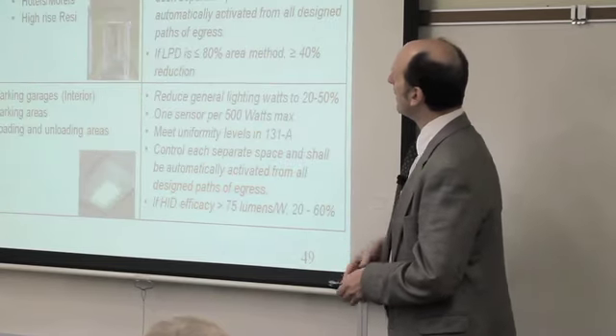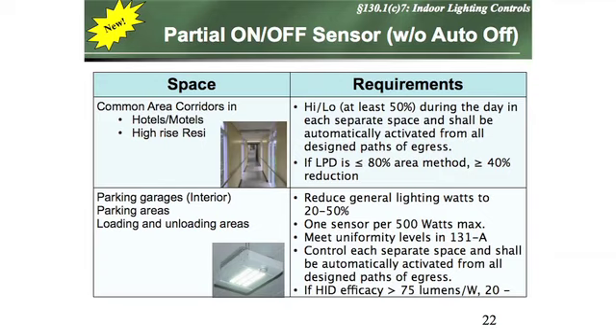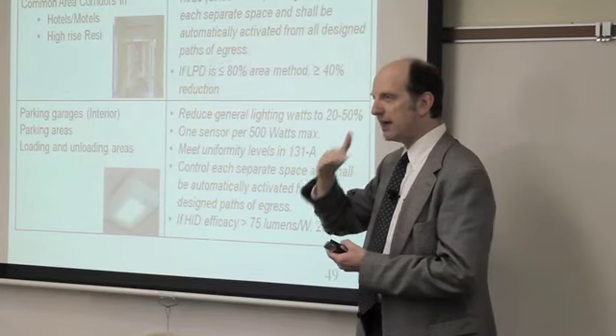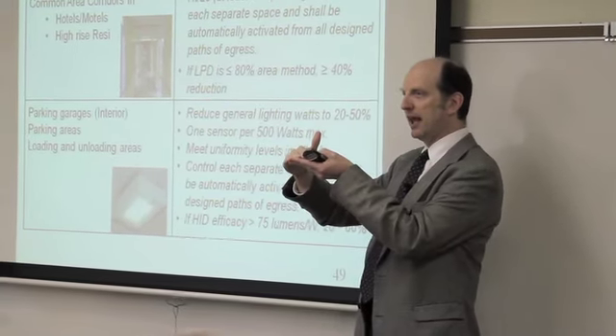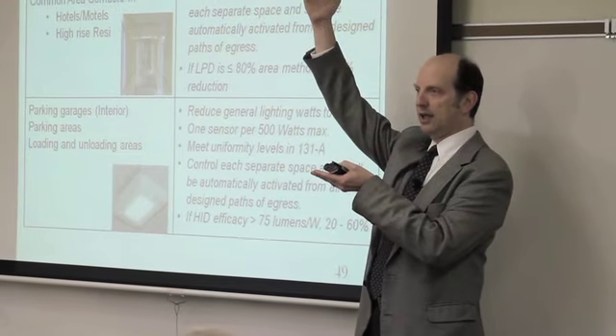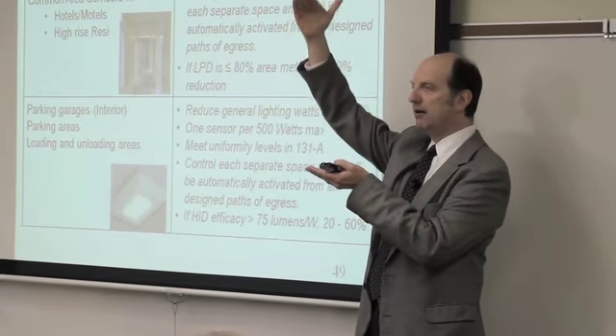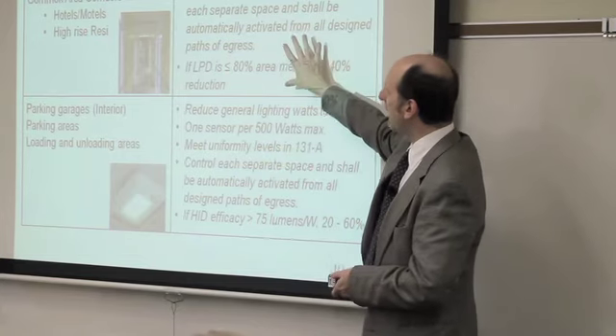All right. That same idea of partial on and off they have for other spaces, except this is where there's no automatic off. So partial on-off for corridors and hotel, motel, multi-dwelling units. There, you never have to go fully off, but you always have to go so that when somebody's in the space, it's lit halfway. When they walk in the space, it goes up to full, and when they leave the area, it goes back to a half level. So we have that here.